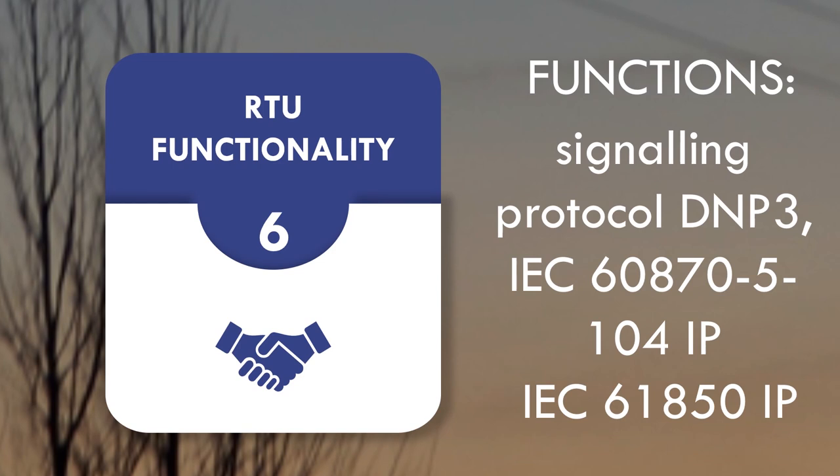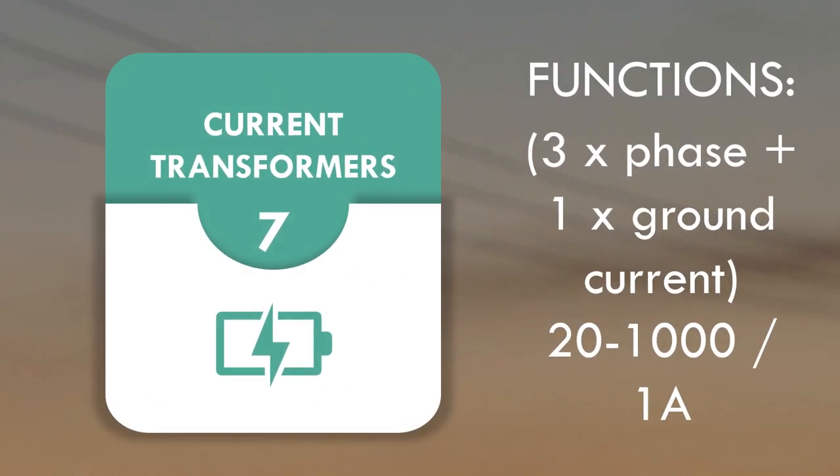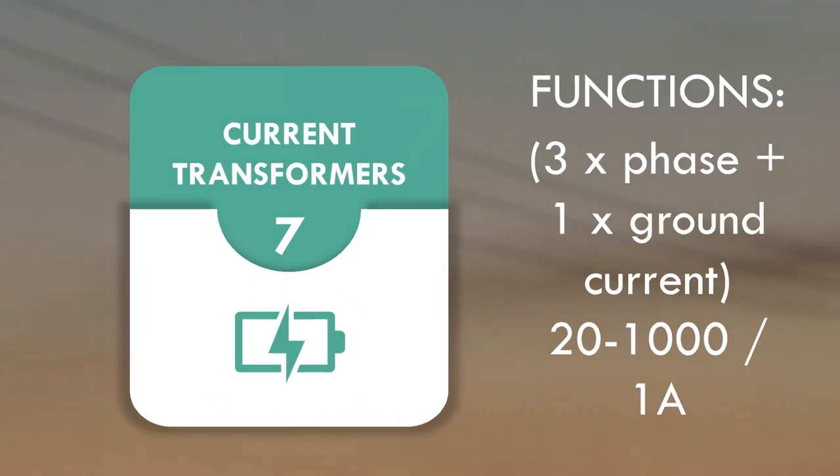Built-in signal protocol: DNP3 Serial and IP, IEC 60870-5-101 Serial, IEC 60870-5-104 IP, IEC 61850 IP. Built-in current transformers: 3 built-in phase current transformers and 1 ground current transformer which is winded 20 to 1 for best ground fault sensitivity.